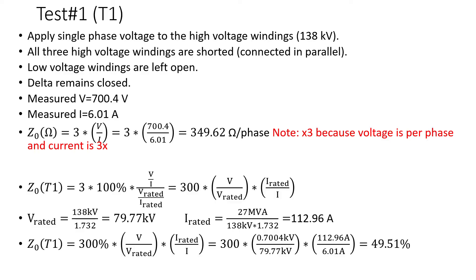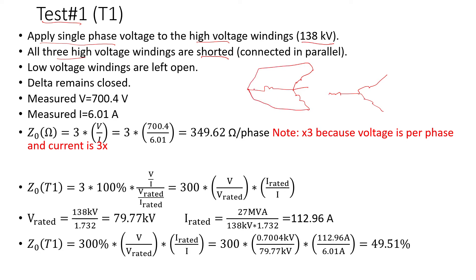Test One: apply single-phase voltage to the high voltage winding — I'm going with 138 kV as an example. All three high voltage windings are shorted, meaning they are in parallel. You short the terminals, then apply single-phase voltage with all the high-side voltage windings shorted to the neutral, and leave the low side open.